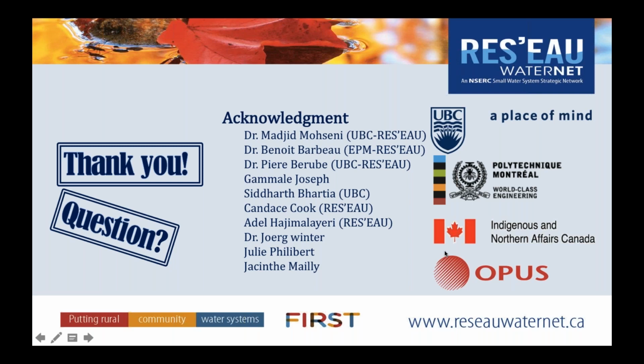Okay. Actually, I'm using the conventional resin, Purolite A8060, which is a strong base anionic ion exchange resin. The only difference is that we didn't do regeneration, so we allow microorganisms to grow on the surface of the resin, so we have a biological mode of this system. But about the backwashing, I can go to that slide.